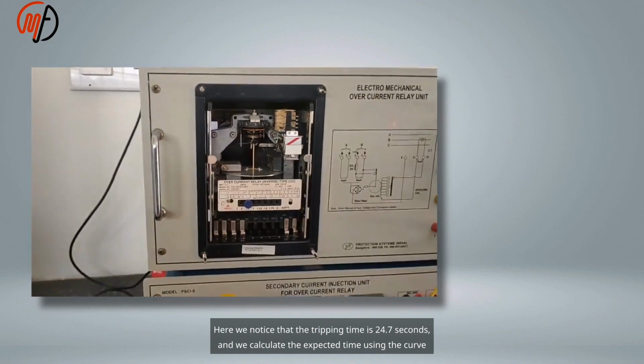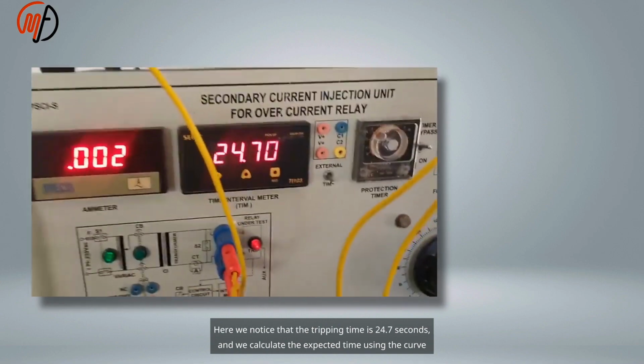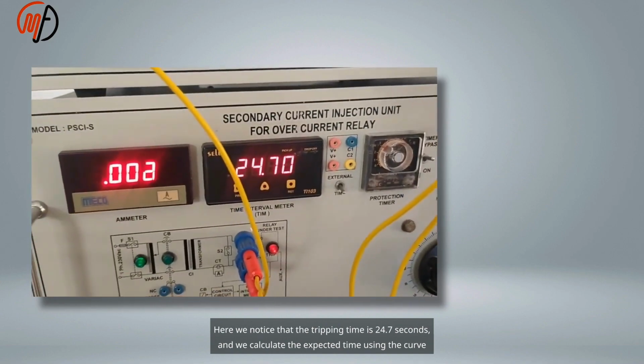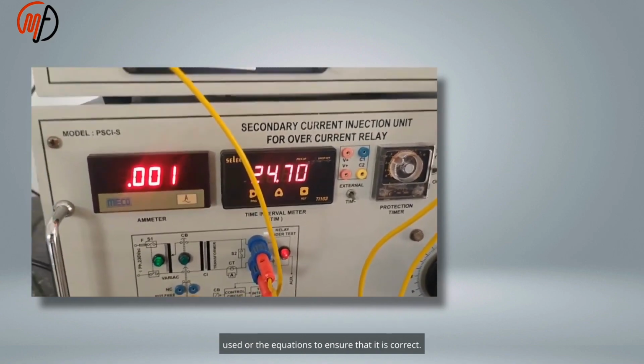Here we notice that the tripping time is 24.7 seconds, and we calculate the expected time using the curve or the equations to ensure that it is correct. We explain the operation of the induction disk relay.